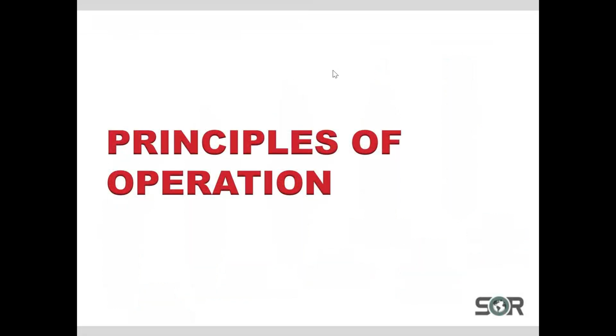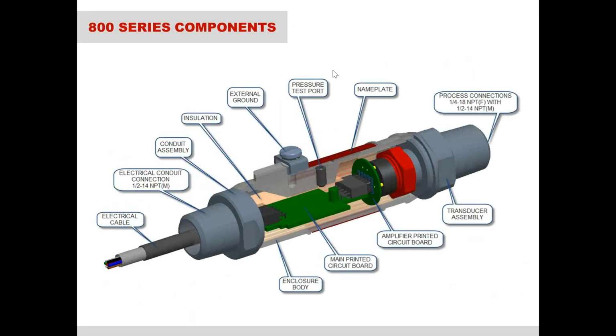First we'll get into the principles of operations of these products. This is a basic cutaway view of the transmitter. The electronics of the 805 and the 815 are slightly different, and that's really the difference between the two. The housing, the process connection, and the sensor itself are the same. The main difference is the electronics and what goes onto that circuit board. The board for the 815 has some different components on there that give it all the features such as HART and Modbus communication protocols and other things like that.